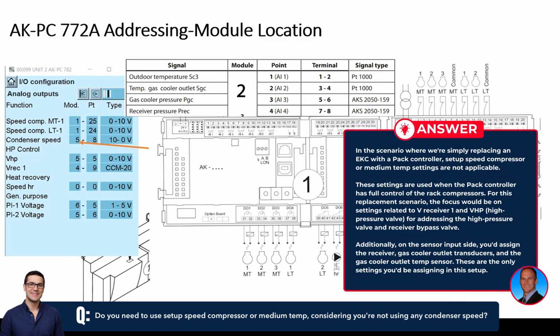Okay. Yep. And then over on the sensor input side, it would be your receiver and your gas cooler outlet transducers, and then the gas cooler outlet temp sensor. So those are the three sensors that you'd be assigning. It should be the only three you're assigning in that setup.